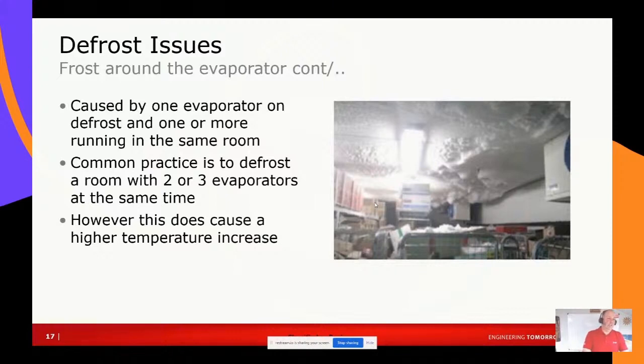The downside is if you defrost all the evaporators at the same time, then you get a slightly higher increase in the room temperature. So it is very much dependent on the application, on the goods being stored in the room.